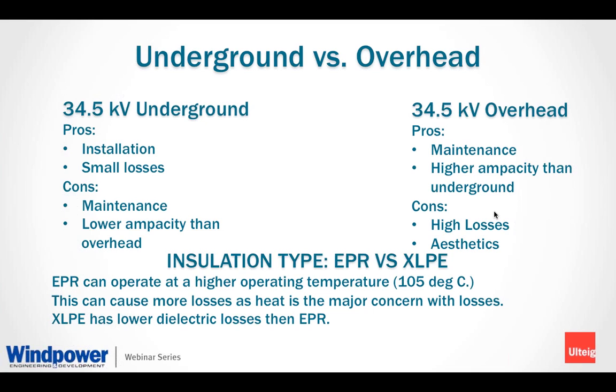And I'd like to talk about the two most common types of underground cable insulation used in these wind farms and throughout the industry. The two types are EPR, which is an ethylene propylene rubber. This type of material can be described similar to an eraser, and that's what is insulating the conductor from shorts and whatnot in the ground. The other type of insulation is an XLPE, which is a cross-linked polyethylene, and it's very similar to a hard malleable plastic type material, if you're not familiar with it.